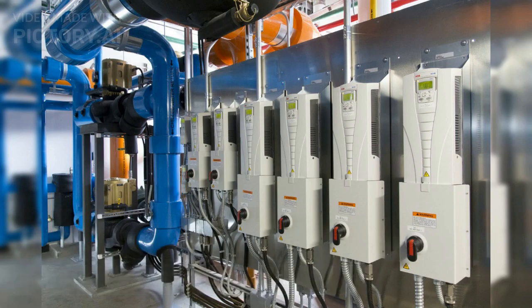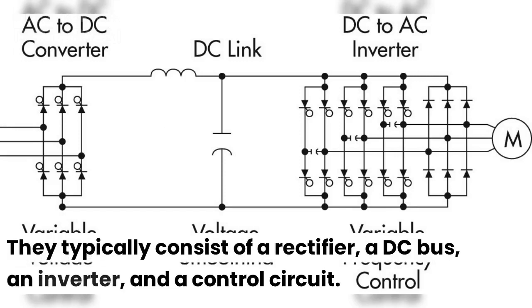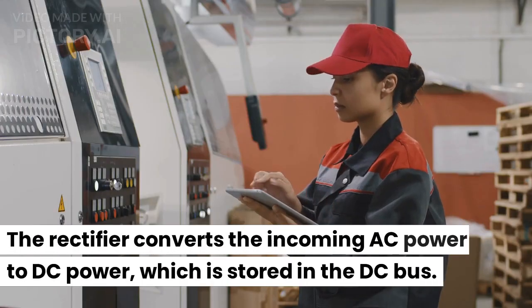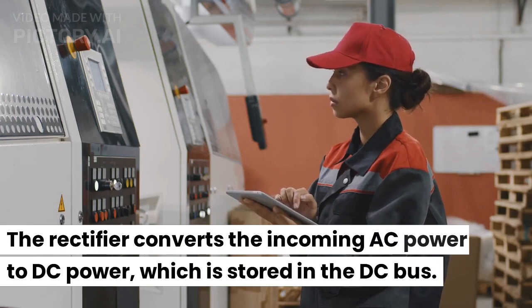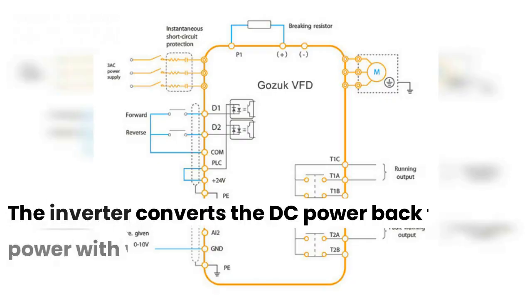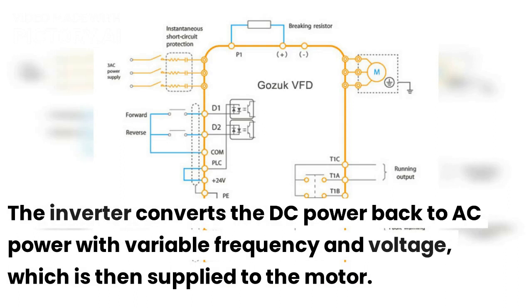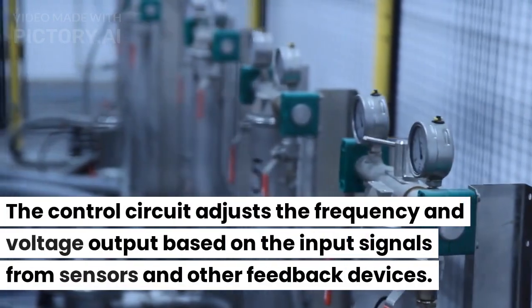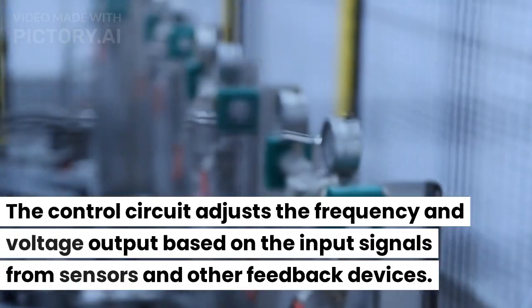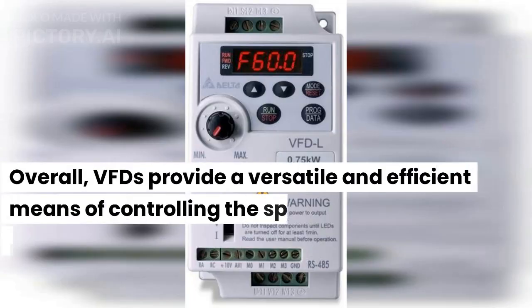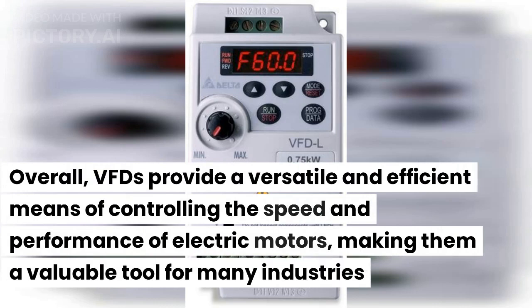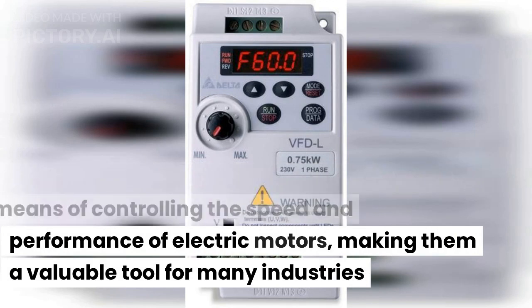units for heavy machinery. They typically consist of a rectifier, a DC bus, an inverter, and a control circuit. The rectifier converts the incoming AC power to DC power, which is stored in the DC bus. The inverter converts the DC power back to AC power with variable frequency and voltage, which is then supplied to the motor. The control circuit adjusts the frequency and voltage output based on the input signals from sensors and other feedback devices. Overall, VFDs provide a versatile and efficient means of controlling the speed and performance of electric motors, making them a valuable tool for many industries.